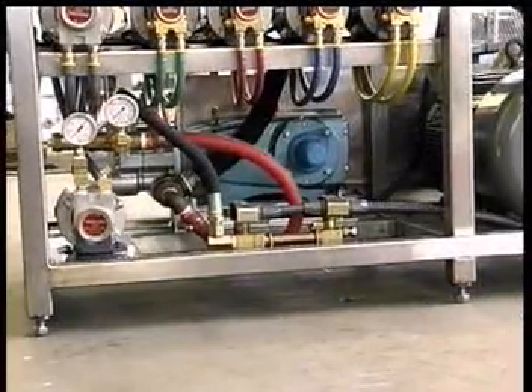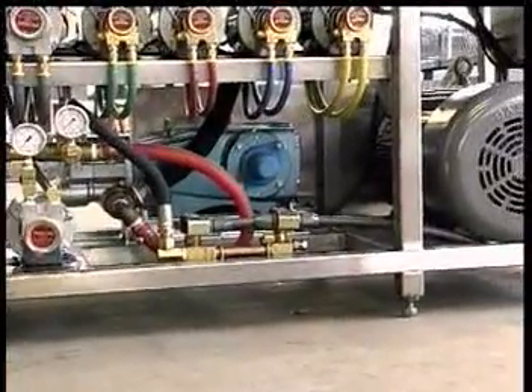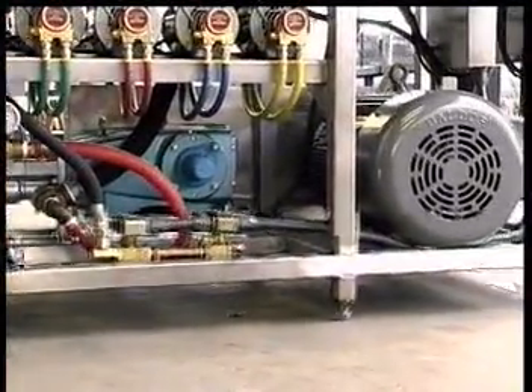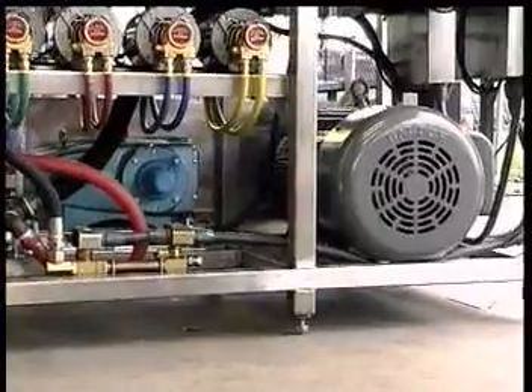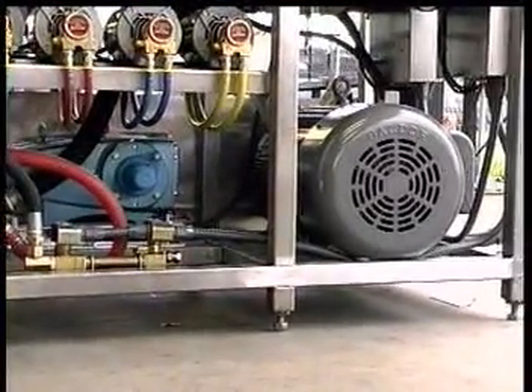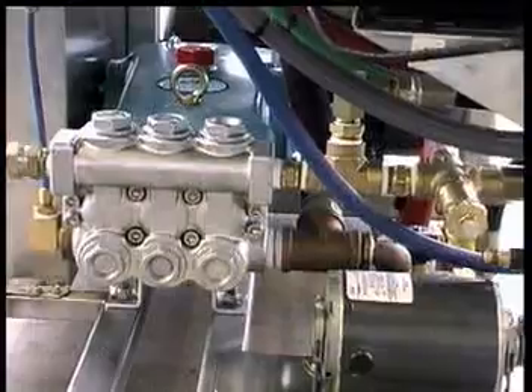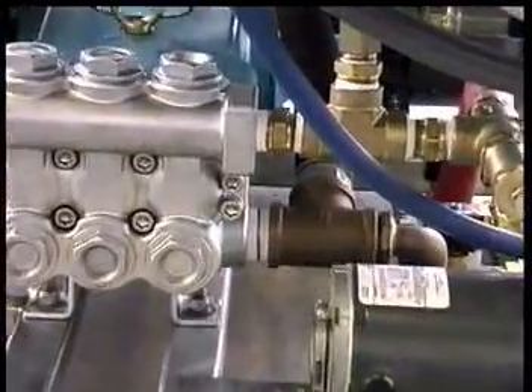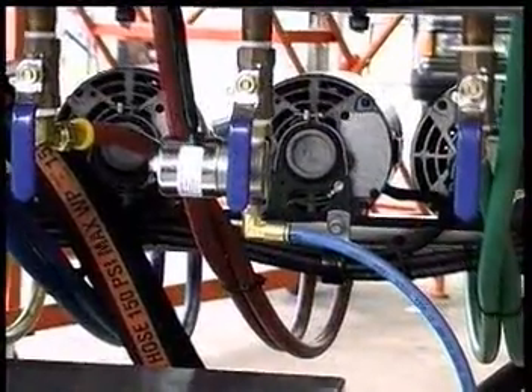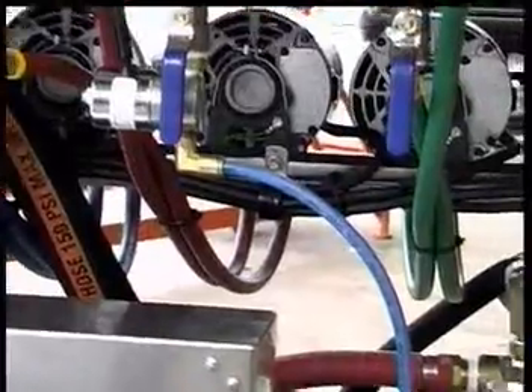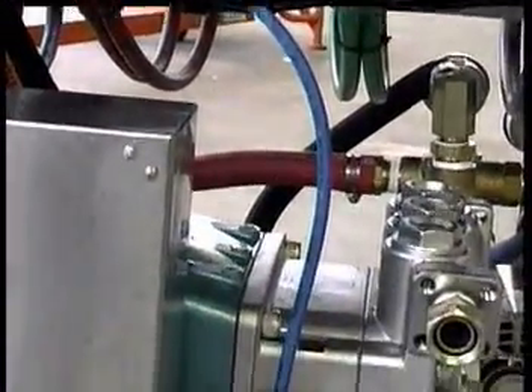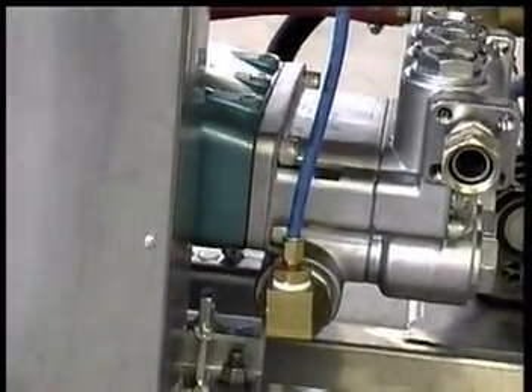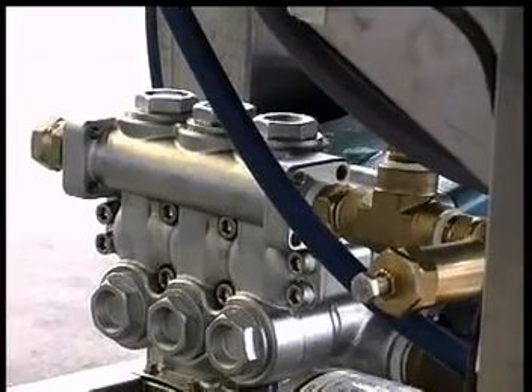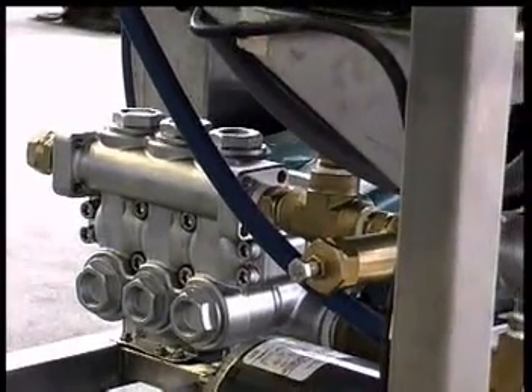A CAT 3535 ceramic plunger pump delivers high-pressure water. It's powered by a 25 horsepower, 220 volt, 3-phase motor and a belt drive system. The pump's inlet is on the bottom side of the pump head. Solenoids controlling high-pressure chemical injection for functions such as wax and high-pressure soap are located on the inlet side of the pump head. The top outlets of the pump head are the high-pressure outlets.